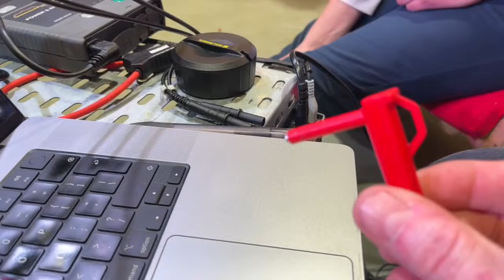We had some great photographs of it actually connected in, making those measurements. We couldn't leave it like that because the front was open, and we couldn't leave it for 7 days with the panel front off. Well, in some instances you're going to have to make tails, take a few blanks out, and stick them through there. They're good because it's a temporary measurement to get the voltage signal.